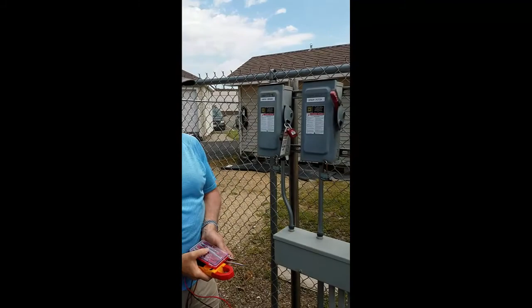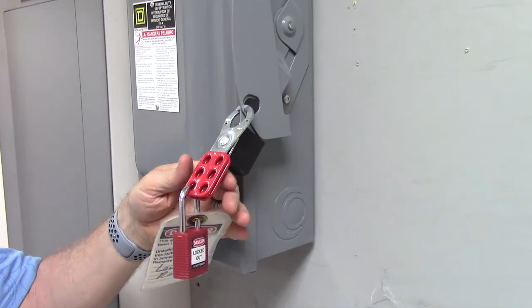Step 11, remove our lock from the building grid service panel. Here inside the building, turn the switch on. Now that we've got our photovoltaic array connected and all of the wires terminated in our AC disconnect, we are going to turn the power on to our sub panel that our array connects to. Take off our lock and our tag and turn the disconnect on.